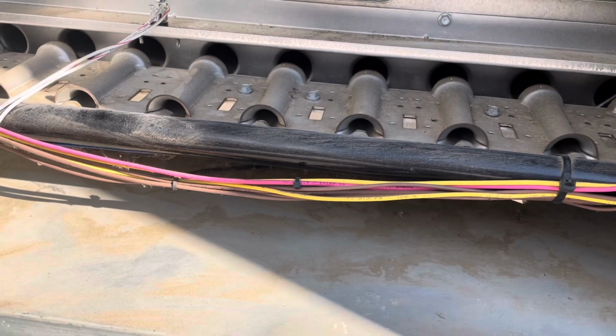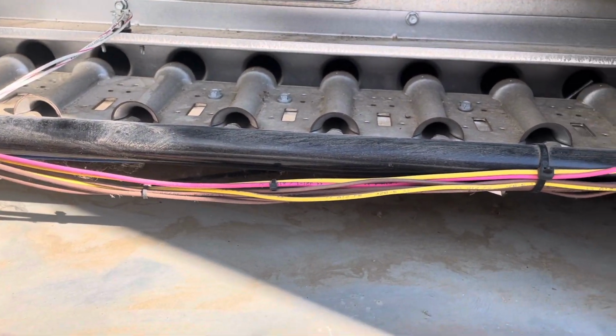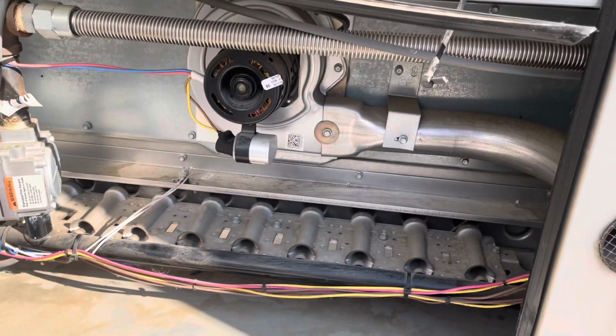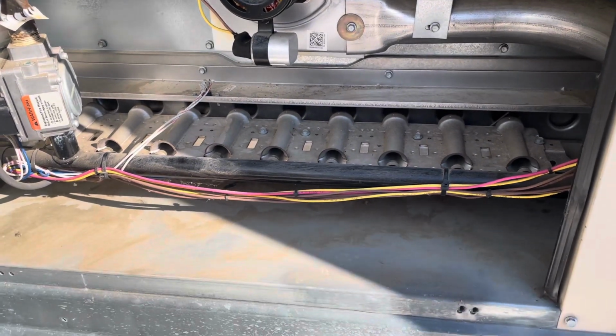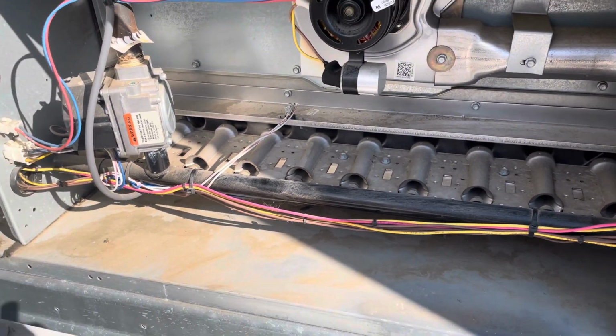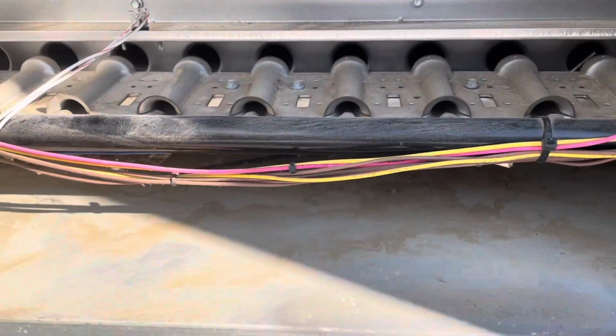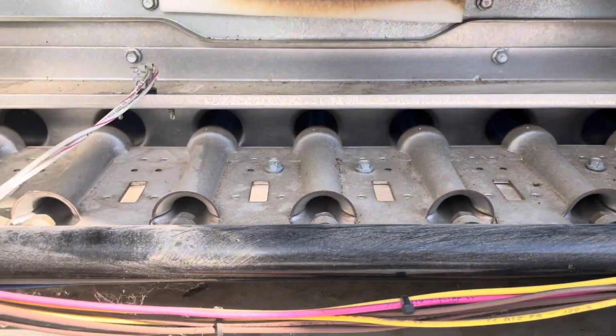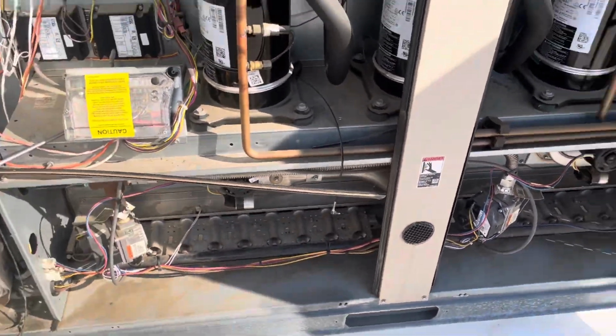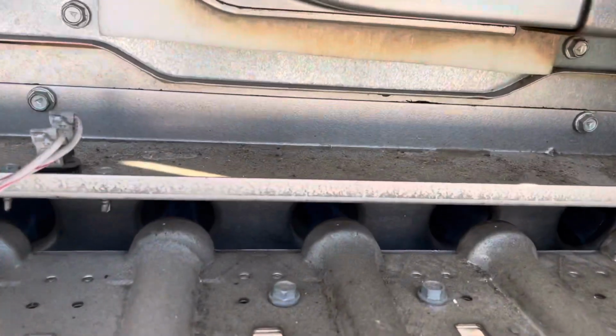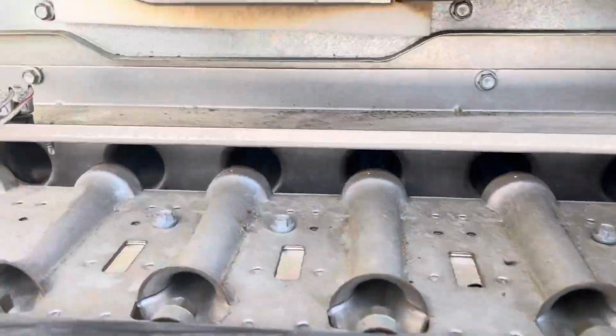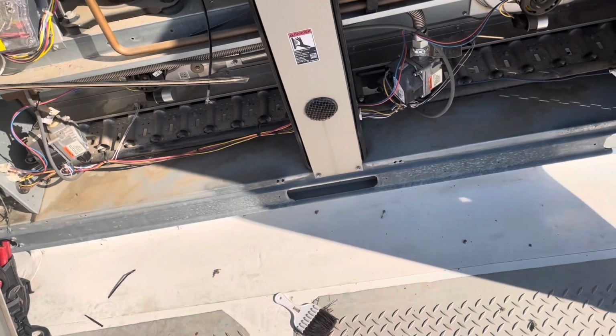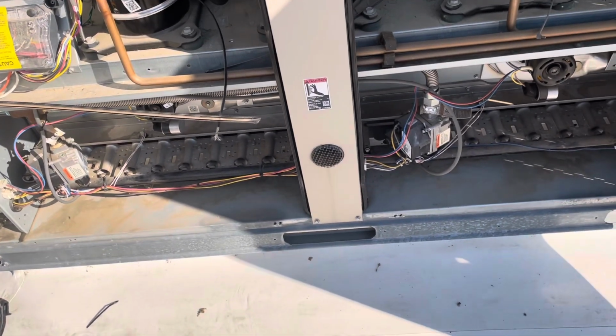Alright, now we wait for a flame. We wait for the pressure switches to close, for the board to pick that up, and then for the spark. And there's our flame. Flame on both sides. So I'm gonna go ahead and turn it off just because it's still warm and I don't want the space to heat up. But yeah, that's pretty much the process. It's very simple.